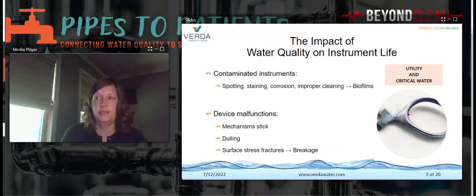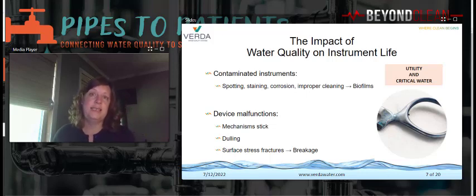So, the impact that water has on instrument life. There are two impacts on instrument life due to water quality: contamination and malfunctions. So let's talk about the contamination. Poor quality water can result in spotting, staining, and corrosion. All three can interfere with sterilization. For example, where hard water spots exist on instrument surfaces, bacteria and biofilms can form and take hold. Stains are like spots, but tightly packed. The color of the stain gives an indication of the predominant mineral content in the water, such as copper or iron. The color of the stain can also give an indication of too high or too low a pH. Like spots, stains are surface regions, and bacteria and biofilms can form and procreate.